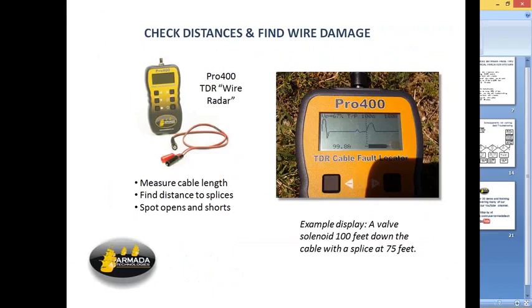And the main picture here shows a little test cable I built up that is 100 feet long with a good splice at 75 feet. So I hook up the wire radar to it, and you can see the picture that it produces. I see a big upward blip at the end, which is the sign of an open circuit. A downward blip is a sign of a short circuit. There are some little cheat cards that go with this. And then you can see a wiggle that occurs between that big blip and where you started, which is on the left.